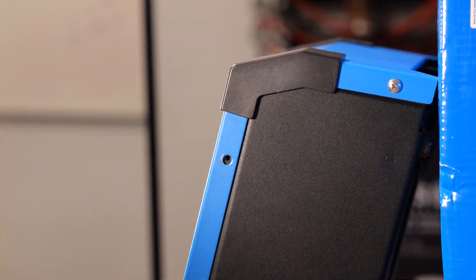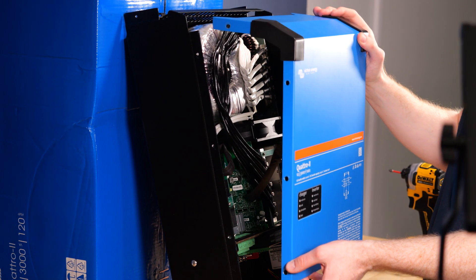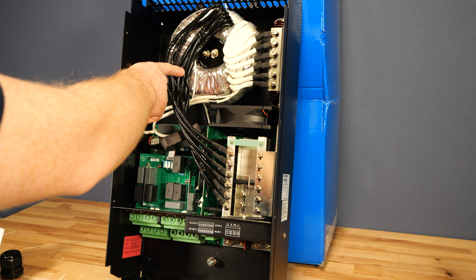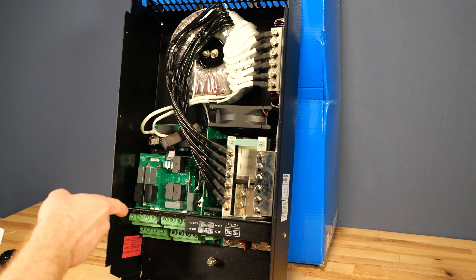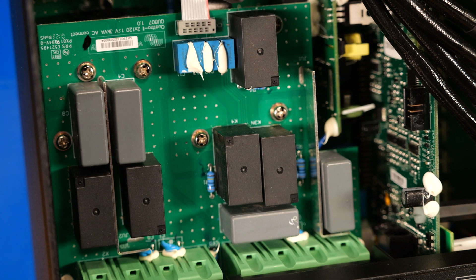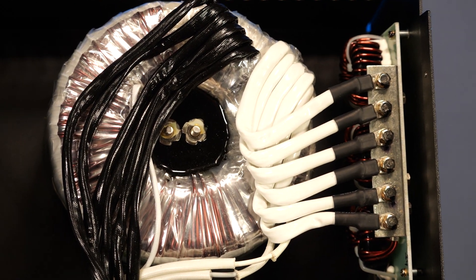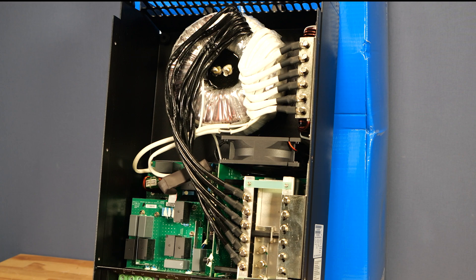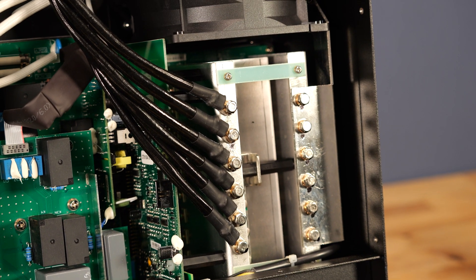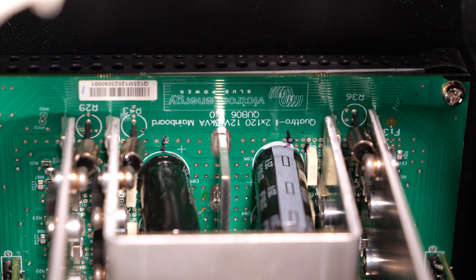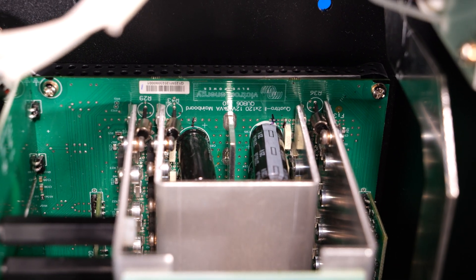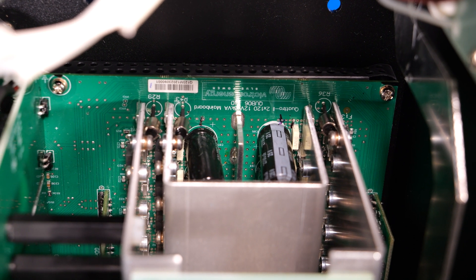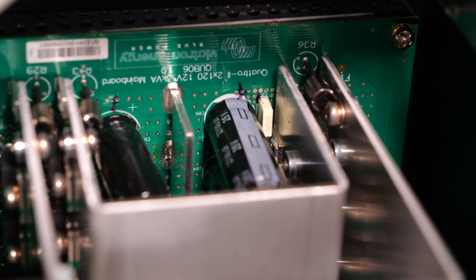Now it's time for everybody's favorite part, time to dig into this machine and see what's inside. So here we can see the H-bridge going up to the transformer to step up the voltage. Everything inside here looks really similar to a multi-plus, except this extra board here for your extra input and output. The Quattro is a transformer-based low frequency inverter. This makes it great for starting up inductive loads like air conditioning. This inverter could easily power a single rooftop air conditioner even without using a soft start, and if you were to add a soft start, you could probably power two of them. What's interesting we found with this inverter was you normally see a really large capacitor bank on the DC side, but this inverter has a really small capacitor bank hidden away under the heat sink for the H-bridge.